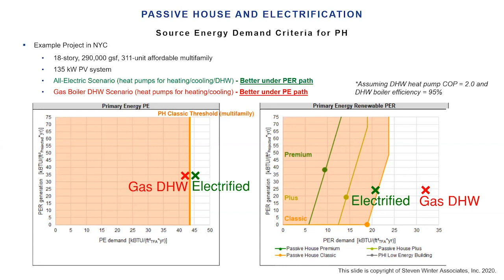The graph on the left is our primary energy, showing the red X or green X for the different building scenarios. Under the PE path, the primary energy path, the gas domestic hot water version of this building is actually performing better and falls within that compliance threshold. The all-electric building, even with heat pumps for domestic hot water, assuming a conservative COP of about 2.0 which could get a bit better, is actually not complying with the PE threshold and is worse than the gas boiler plant scenario.